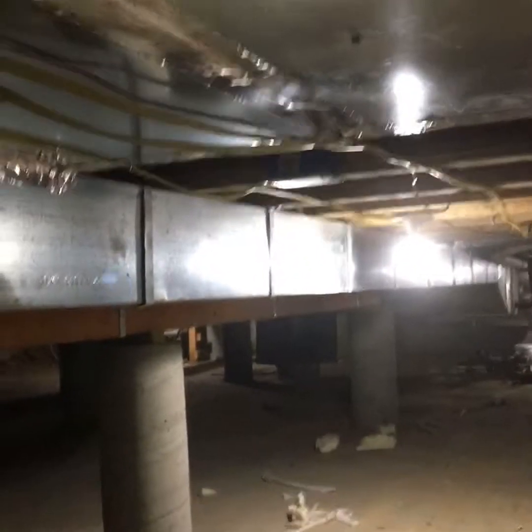But what they did originally, there was this return pipe right here that was an 8 by 20. We pulled it out, installed a 10 by 24. This is our metal pan. It comes over and ties into that box you saw upstairs. All this has been sealed off and connected. And then we come on down.